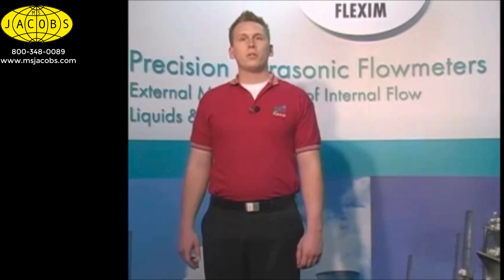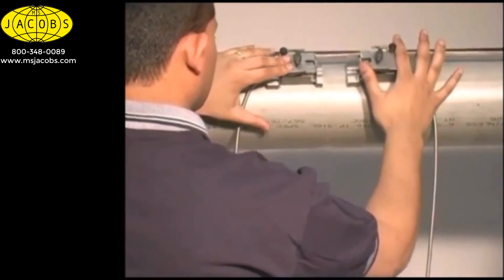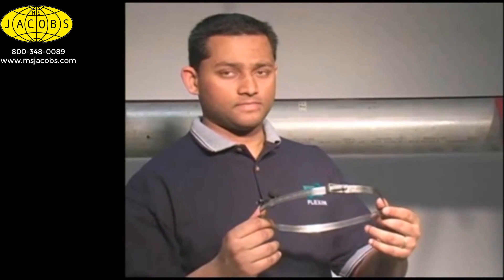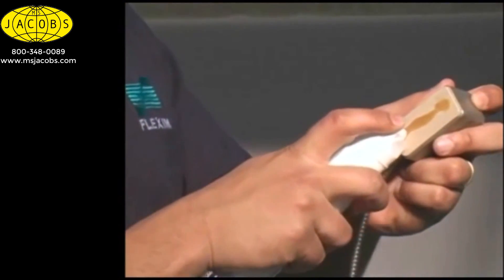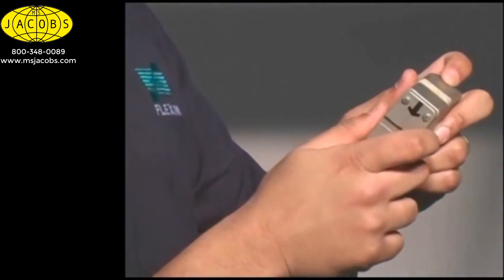Now we can mount our first transducer. We don't want to mount both transducers at this point because we don't know yet how far apart to put them. We have several different mounting options available. For permanent installations, we have a permalock track, which is especially recommended to protect transducers from the elements. Even though all Flexim transducers have stainless steel housings, the permalock tracks provide an added means of protection. For temporary mounting, we have several different sizes of magnetic mounts. For indoor applications, permanent or temporary, we can use Flexim mounting straps. We're going to use these for our demonstration. Place a small amount of coupling gel on the head of the transducer — a quarter inch bead down the center is perfectly fine. We want to be careful not to use so much that we have lots of acoustic coupling gel oozing out the sides when we put the transducer on the pipe, or we might inadvertently lose some of our signal.